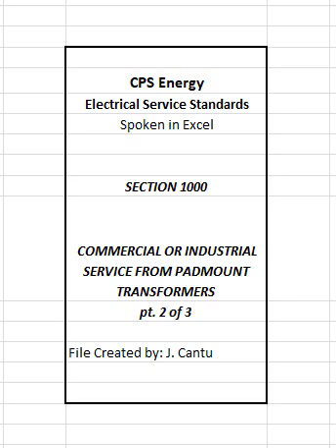B. Transformer slab. The transformer shall be mounted on a steel-reinforced 2500 psi regular concrete slab built by customer to CPS Energy specifications. In addition, the provisions of 1 through 5 below will be applicable for construction of transformer slabs. 1. The top of the slab shall be a minimum of 6 inches and a maximum of 12 inches above final grade. 2. There shall be no pipes, conduits, etc. under the slab except those necessary to supply primary to the transformer, those required to supply the electric load, and the 2-inch conduit that may be required for metering that is to be stubbed out from the concrete slab.